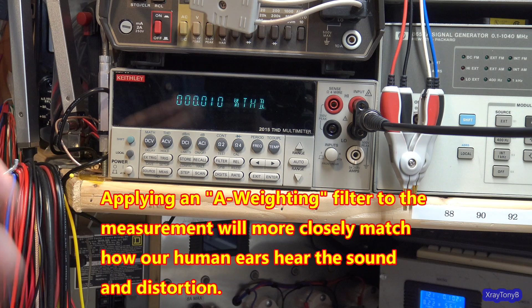Now this one can go a step further because it can actually filter individual harmonics. Like I can have it only look at the second harmonic or the third harmonic and ignore all the ones above that. Or I could have it look at however many harmonics I want. I can also put weighting into it. I'm not going to talk about what weighting is, but it's distortion that is closer to how your ear hears the sound. It's math that it applies to it.